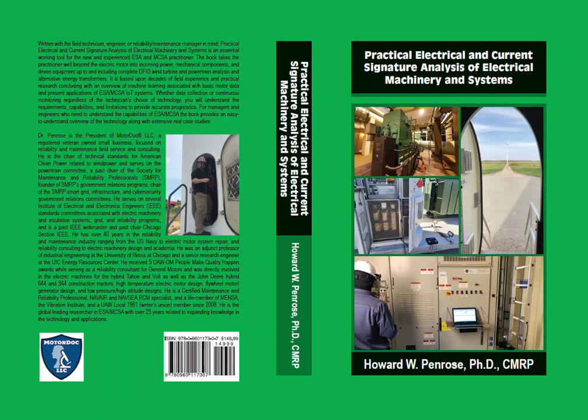In effect, if I look at a belt application, belt slip frequencies, and static eccentricity, I can identify that a belt or sheave is worn, belt tensioning is too tight, the sheaves are misaligned, the motor has soft foot, or any combination of these conditions. This understanding became much more valuable several years later.